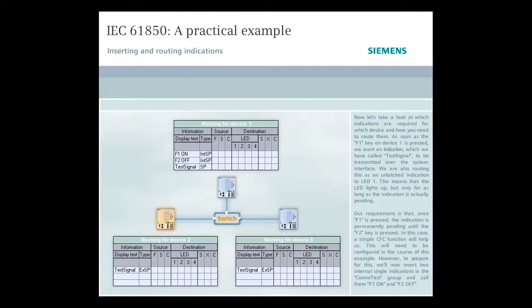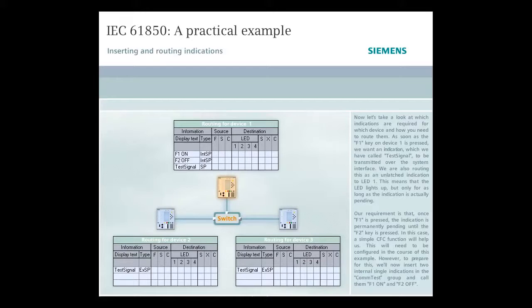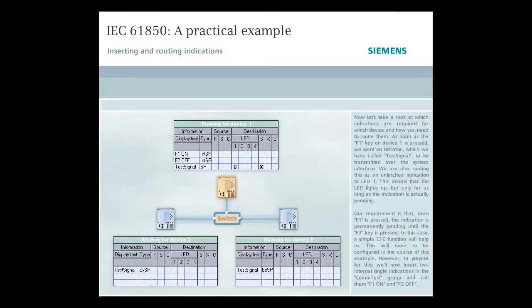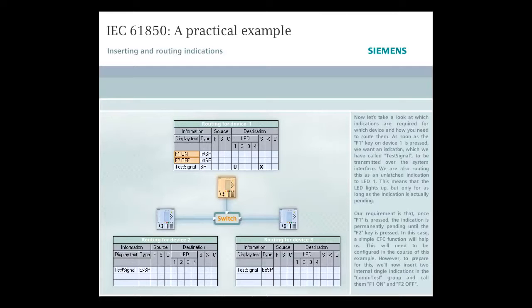Now, let's take a look at which indications are required for which device and how you need to route them. As soon as the F1 key on Device 1 is pressed, we want an indication which we have called Test Signal to be transmitted over the system interface. We are also routing this as an unlatched indication to LED1. This means that the LED lights up, but only for as long as the indication is actually pending. Our requirement is that once F1 is pressed, the indication is permanently pending until the F2 key is pressed. In this case, a simple CFC function will help us. This will need to be configured in the course of this example. However, to prepare for this, we'll now insert two internal single indications in the Com Test group and call them F1 On and F2 Off.